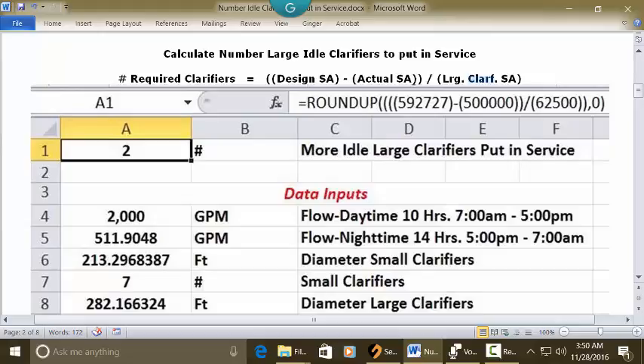Just a couple of clarifications: if we did not use the Roundup function, with whole numbers we would have gotten one, because the answer is 1.48 and it would have rounded down. So in order to give us the next highest full clarifier, we use Roundup. Also, by putting in two full idle clarifiers, it actually brings the gallons per day per square foot below 2.75 — it puts it at 2.6.